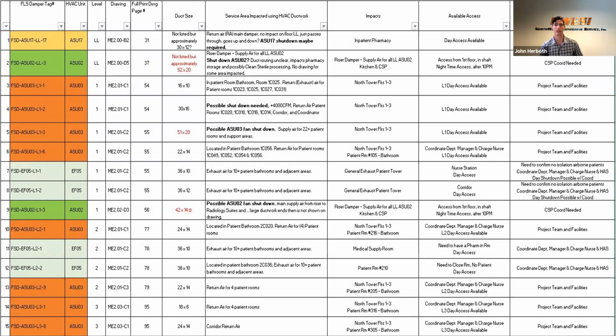Problems. And so you start taking a look at the duct sizes. I tend to take a look, as you can see in one of the columns that I have them in red, for the ones that are getting a little bit large. My rule of thumb is 4 square feet and above. So that 24 by 24 is when you start saying, hey, we should start taking a look at airflow through this to make sure that we don't impact systems. Obviously, the higher risk goes to ORs and places where the occupants have more critical nature spaces and services.